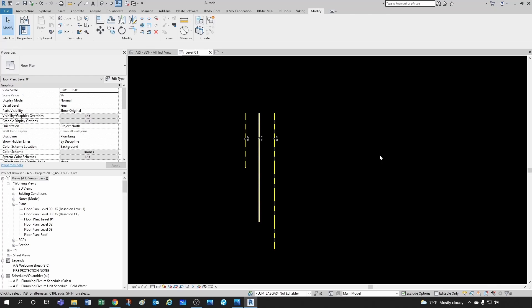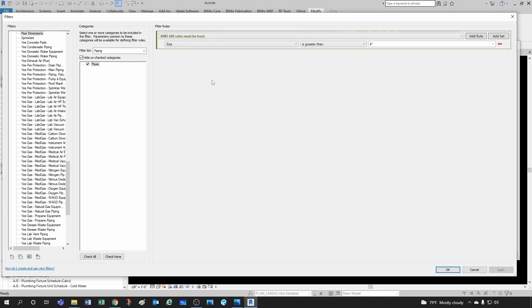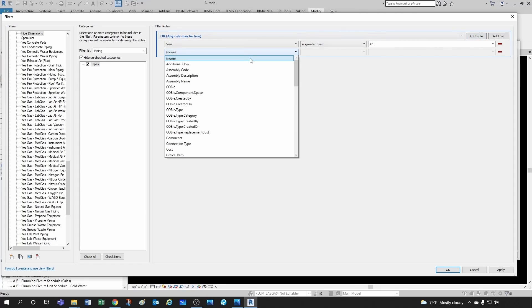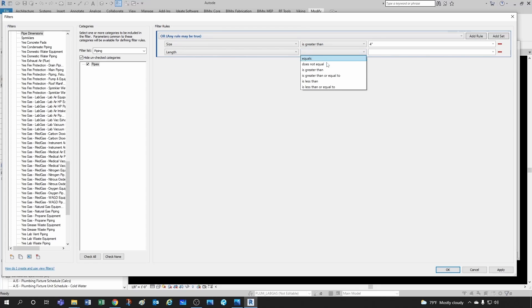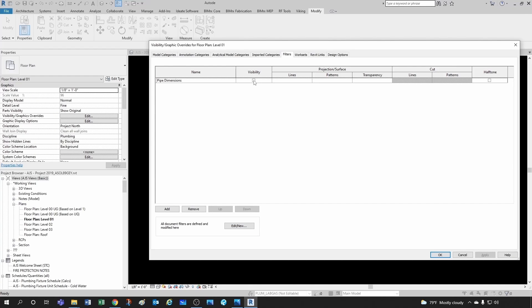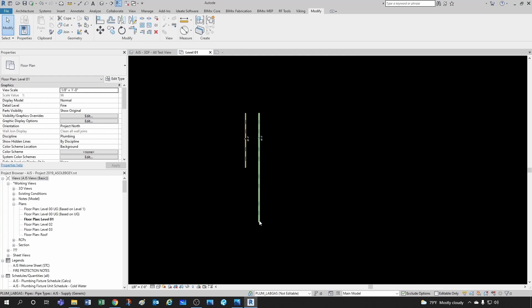Let's go further. I got rid of the large pipes, but I also want to get rid of very long pipes. I'll hit VV again, edit my filter, and add a rule. By default this is set to AND, but I'll switch to OR and add a rule: pipe length is greater than 40 feet. Now I'm telling Revit to select any pipe with a size greater than four inches OR any pipe with a length greater than 40 feet. Clicking OK, the pipes longer than 40 feet disappeared as well.